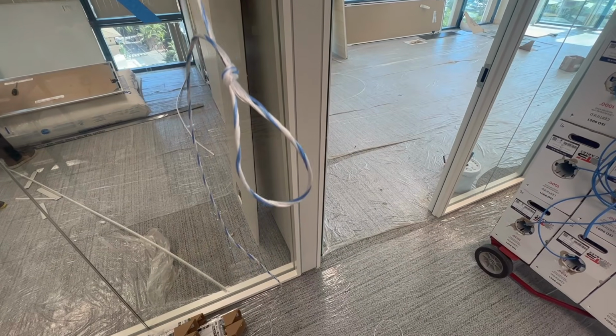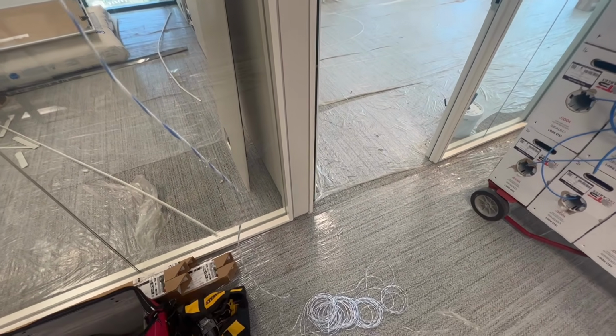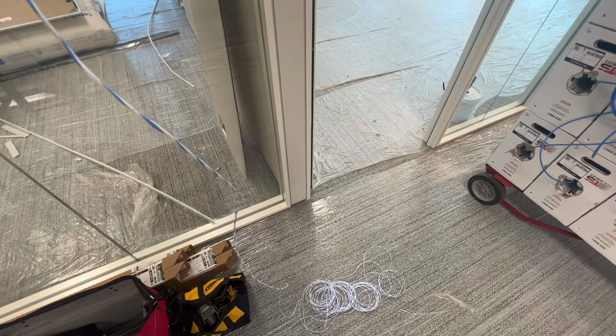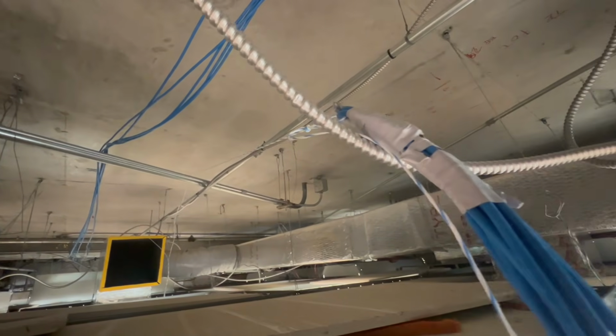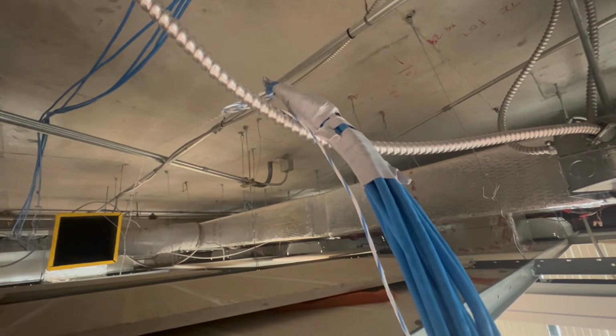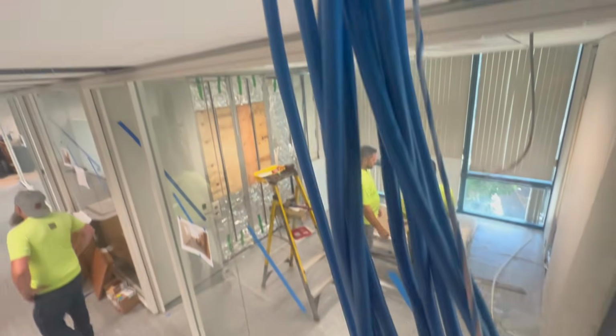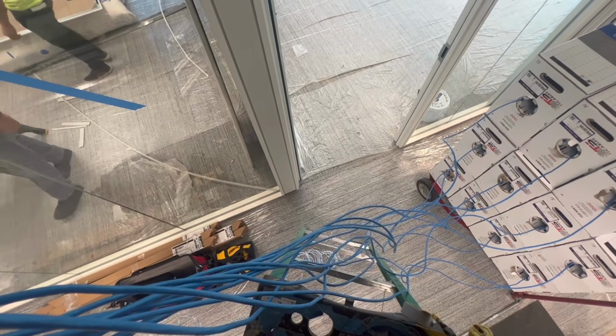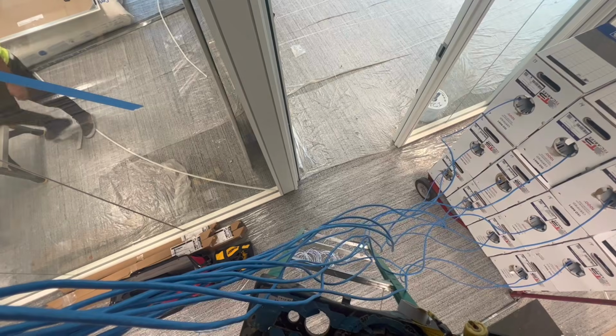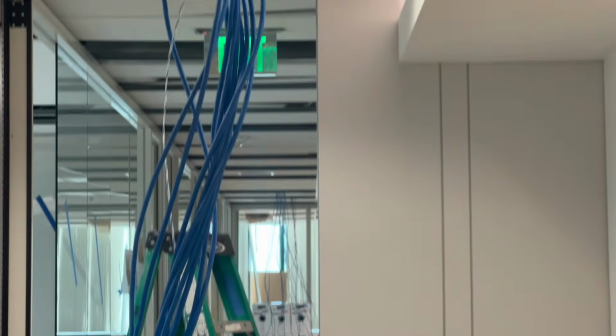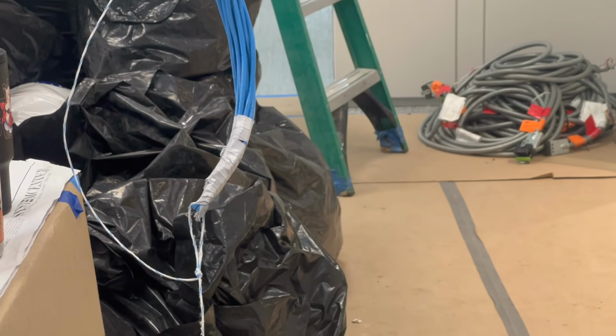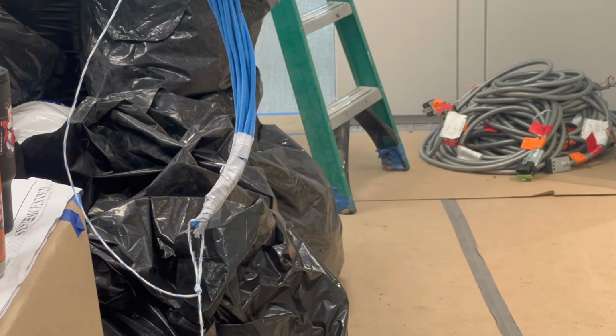I'll tie a loop to it and leave a lot of slack. I'll attach all my cables to that loop, go to the other end of the hallway, and pull on the nylon string. All 12 boxes feed out at once, and before you know it you've got 24 wires down this hallway, no problem at all. Much easier than the method I just showed you.